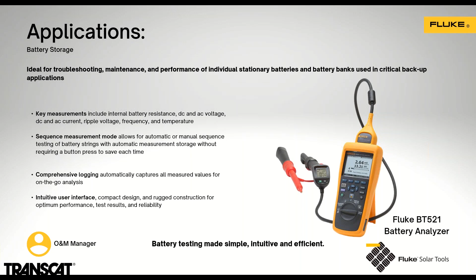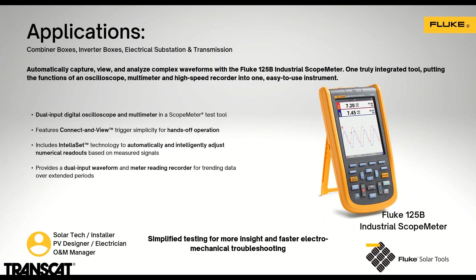Now, we mentioned scopes. Again, the scope is going to allow them to check the output on those combiner boxes if needed, especially the inverters, and even into the substation and transmission. A scope lets you look at that waveform, so if they're really trying to isolate and determine if an inverter is outputting correctly, this is the tool for them—being able to capture that waveform and voltage. We definitely want to get them thinking about having a scope in their truck for those solutions.